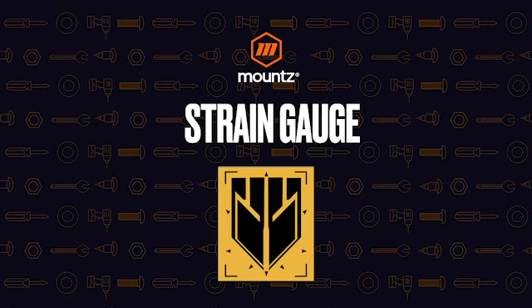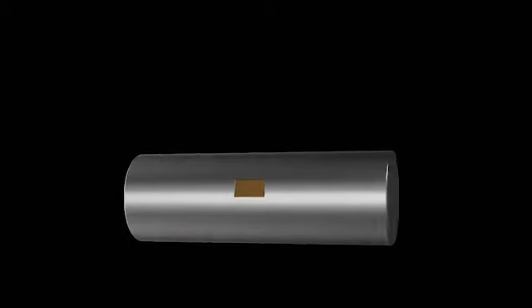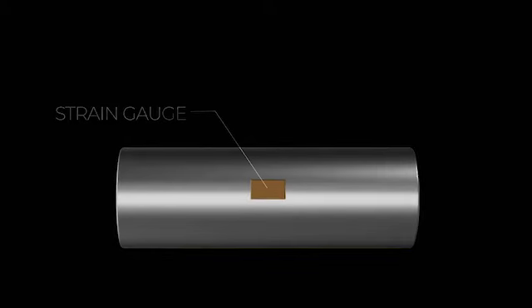And this particular circuit is then laminated onto a piece of stock. As we apply torque to that stock, there is torsion that happens, and it changes the resistance that we see within the strain gauge because it's actually changing its geometry as that stock is being applied with torque. And so we basically are developing a correlation between the amount of deflection that may be happening in the strain gauge to the amount of torque that is being applied. And this animation can kind of help explain that.